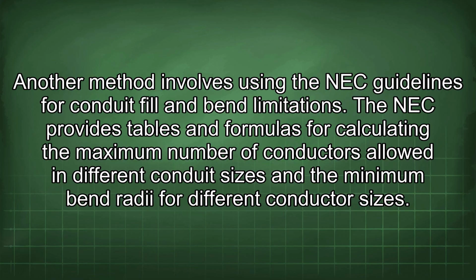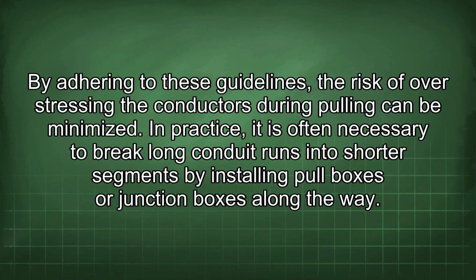The NEC provides tables and formulas for calculating the maximum number of conductors allowed in different conduit sizes and the minimum bend radii for different conductor sizes. By adhering to these guidelines, the risk of overstressing the conductors during pulling can be minimized.